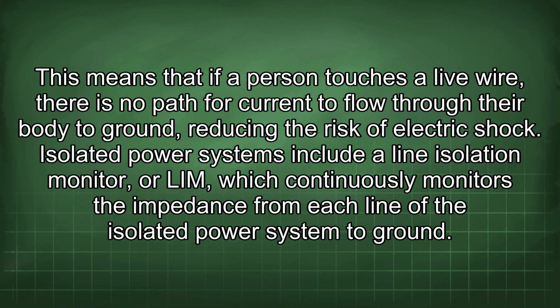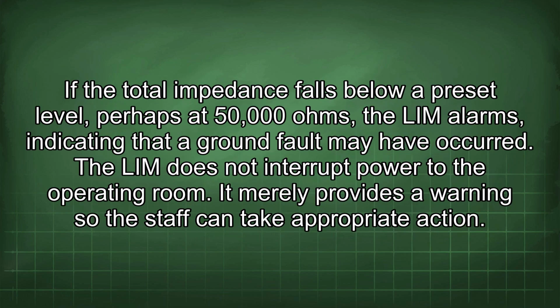Isolated power systems include a line isolation monitor, or LIM, which continuously monitors the impedance from each line of the isolated power system to ground. If the total impedance falls below a preset level, perhaps at 50,000 ohms, the LIM alarms, indicating that a ground fault may have occurred. The LIM does not interrupt power to the operating room. It merely provides a warning so the staff can take appropriate action.